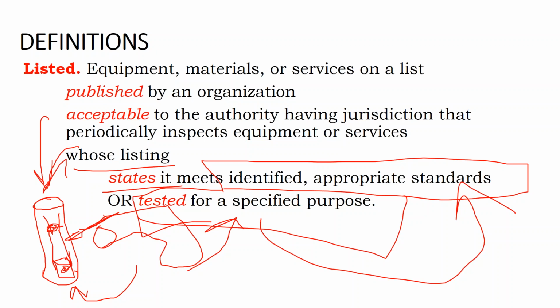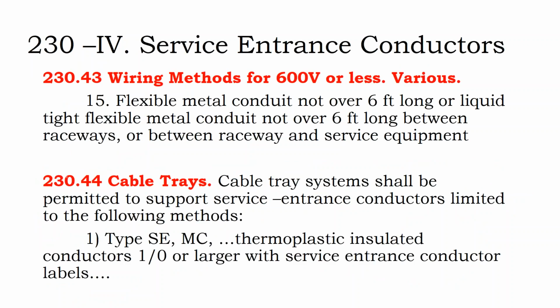And that is intended for direct burial cabling, or even underground deep sea welding operations. But it doesn't necessarily mean that it's listed for your microinverter branch circuits up on a rooftop. It may not have the same physical protection requirements. So if you're borrowing components from a different industry because you think it's a better solution, that's when you really need to read the listings to make sure you're not borrowing something from the direct burial industry and then trying to use it on a raceway up on a rooftop.